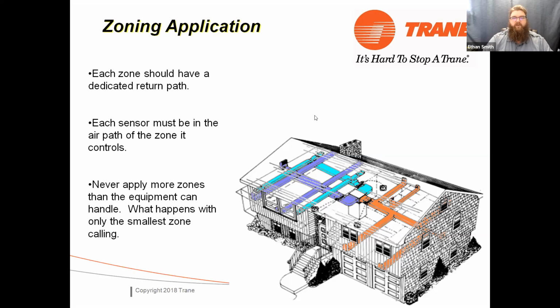Lastly, never apply more zones than the equipment can handle. The reason for this is what happens when the smallest zone calls for the equipment to run. Okay, we have to take that into consideration. So while a lot of zoning panels will accept 5, 6, 7, 8 zones, we've got to think about what happens when that small zone calls and it turns the equipment on. How much excess air are we going to have to deal with? We'll talk about that a lot here in just a second. We talk about air relief strategies.